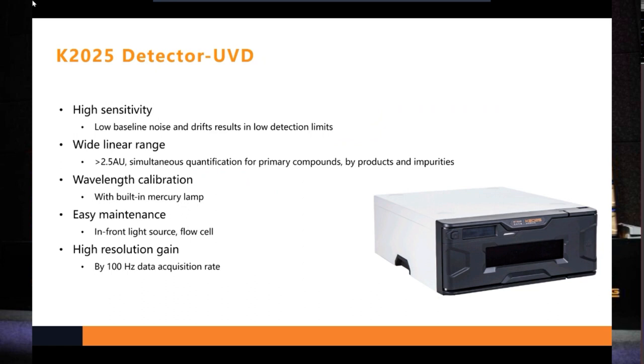The next unit is the detector. UV detector is always the most frequently used detector in all kinds of analysis. The UV detector of K2025 has a very high sensitivity and wide linear range, so that a simultaneous quantification of primary compounds, byproducts, and impurities can be realized. The wavelength calibration can be performed with the built-in mercury lamp. The lamps, the light source and the flow cell are placed in front, so we can easily replace them. And the UV has a 100 Hz sampling rate. This is the basic specs of the UV detector.